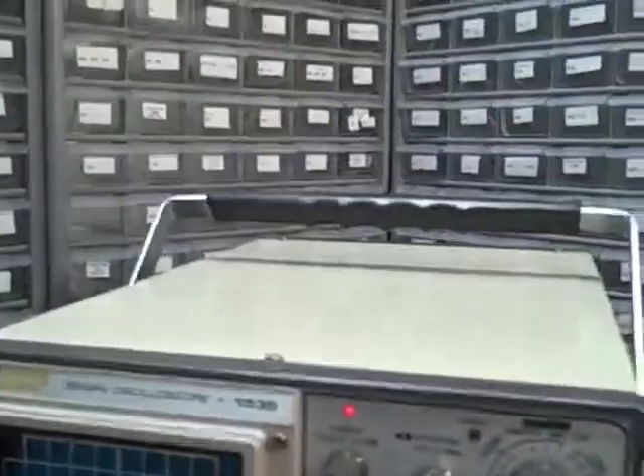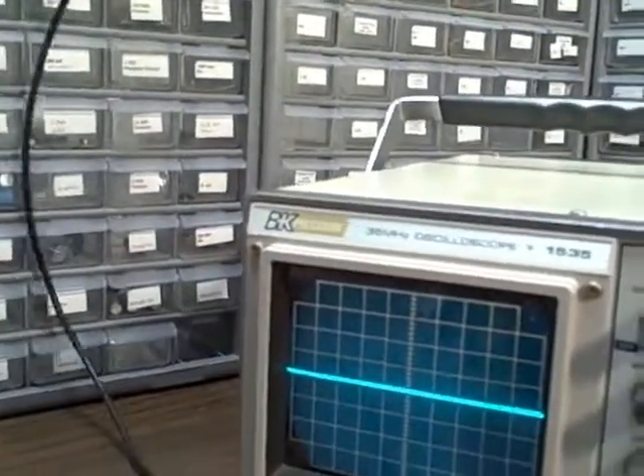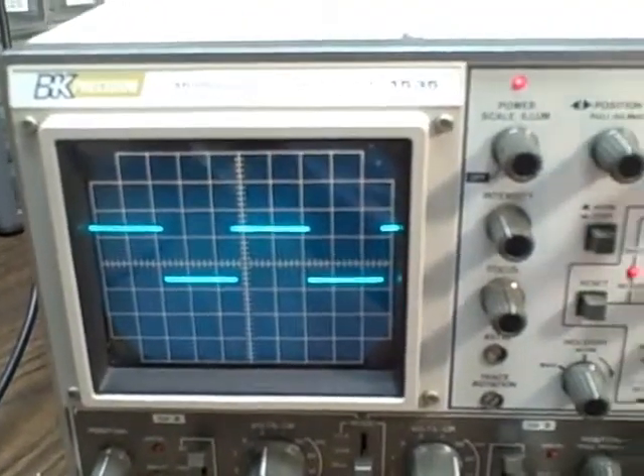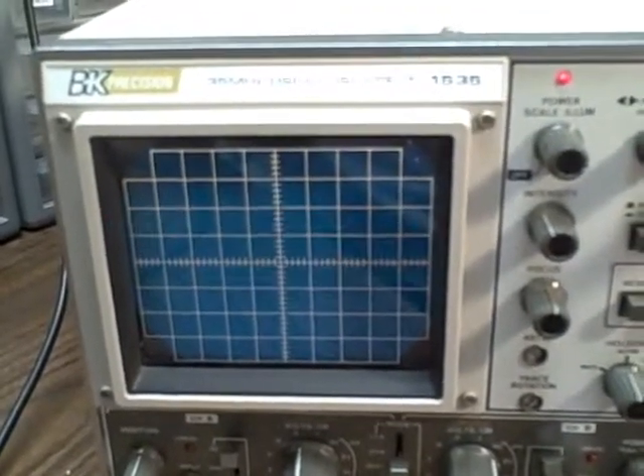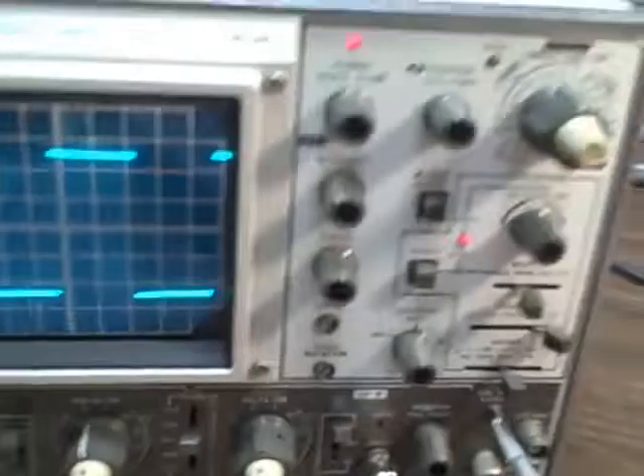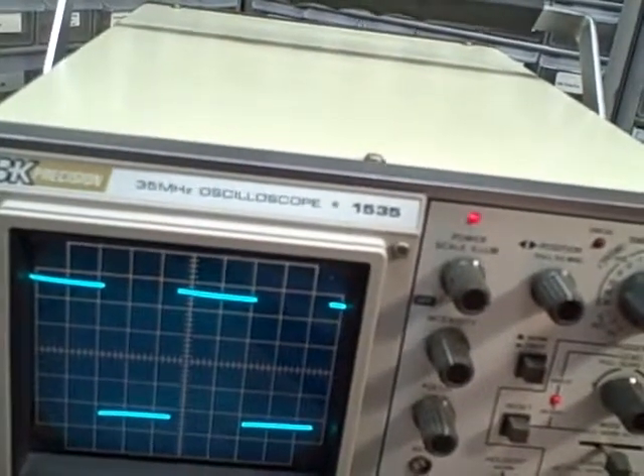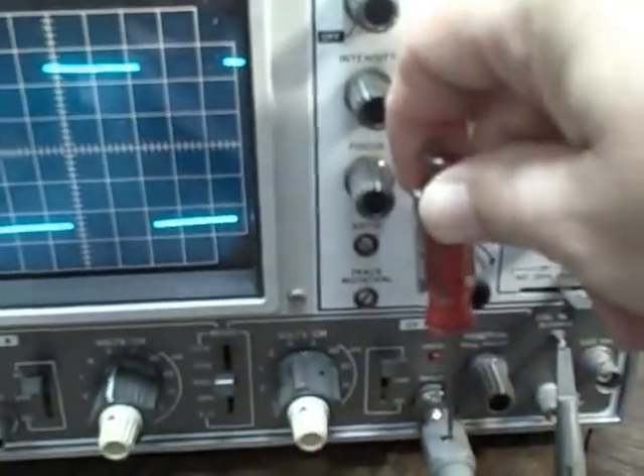We also have a working probe calibration point. We are connected up to the calibration point and we can see that we're getting our 1 kHz signal on there. At this point, let's put ourselves in times 10 mode. We would now adjust our probe to give us the squarest looking wave — let's turn this over so I can get to it. Squarest looking wave — I would adjust the probe point.